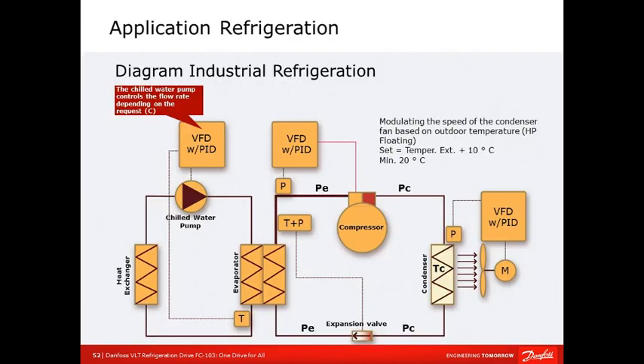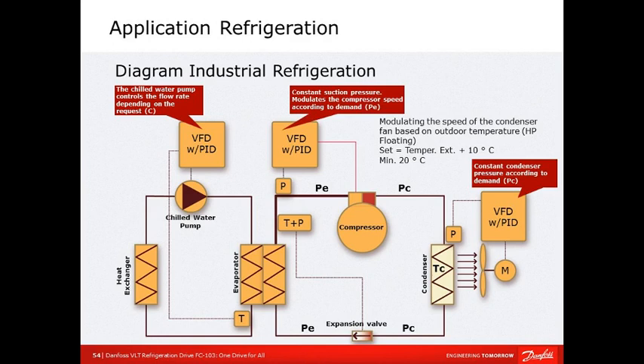This is an example where, if we just look at the red boxes, what was the VFD doing in these cases? They're showing on the far right, with the condenser, we're monitoring the pressure according to demand, and then you can modulate the speed based on the set point, for example. So again, the same variable frequency drive, the FC-103, can be used in all the applications that you have in your industrial refrigeration system.